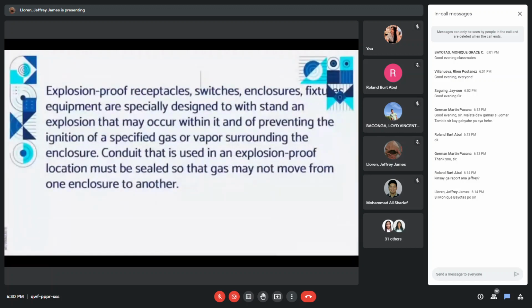Explosion-proof receptacles, switches, enclosures, fixtures, and equipment are specially designed to withstand an explosion that may occur within it, and to prevent the ignition of a specified gas or vapor surrounding the enclosure. Conduit that is used in an explosion-proof location must be sealed so that gas may not move from one enclosure to another.